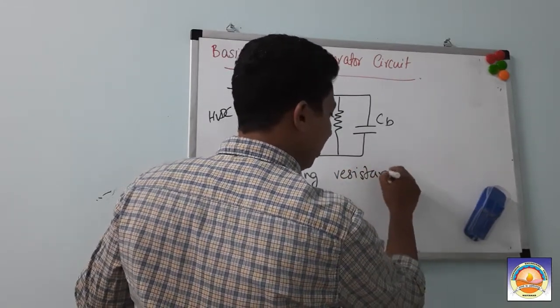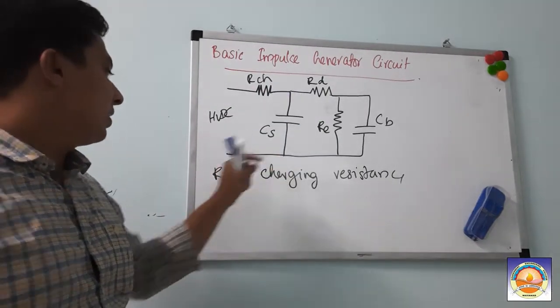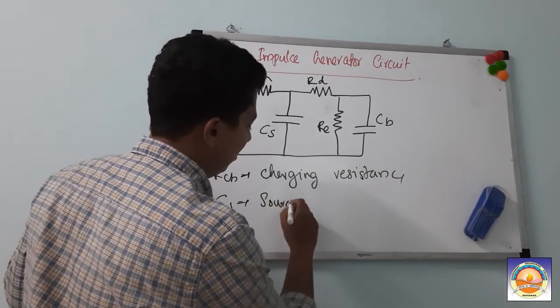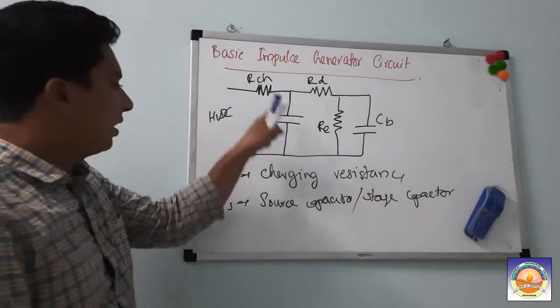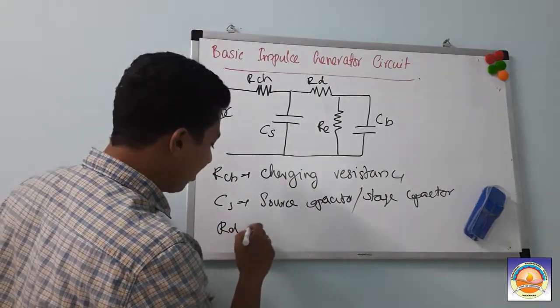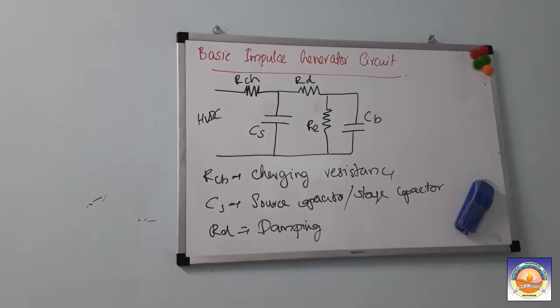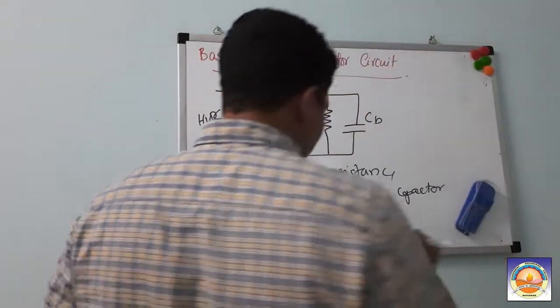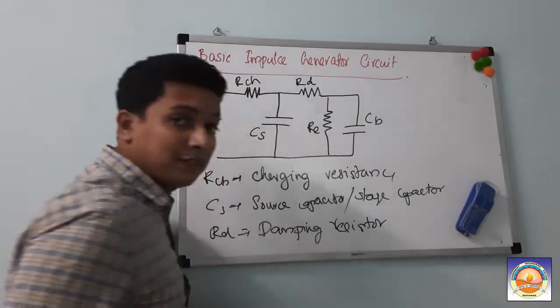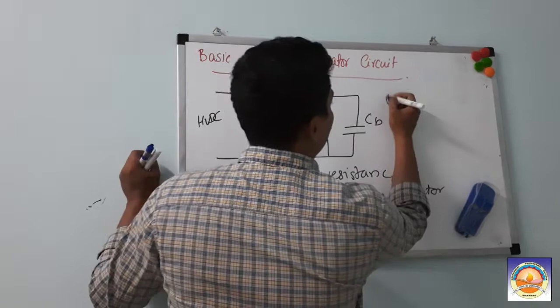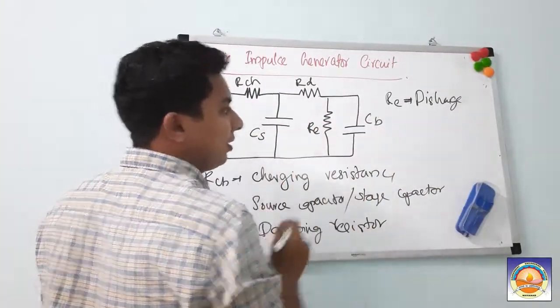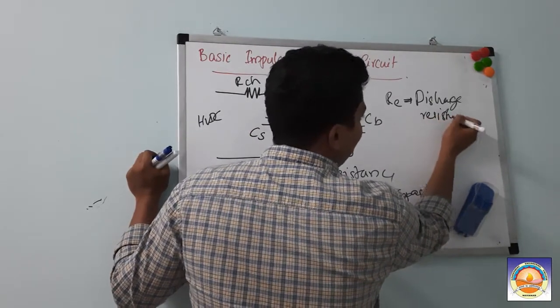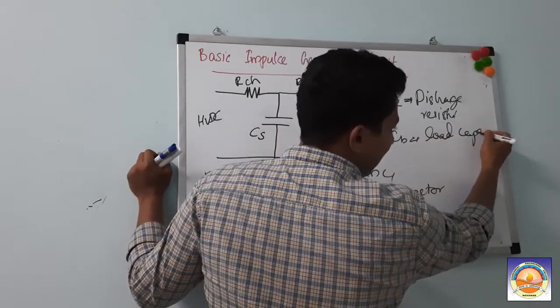The purpose of RCH is that when high voltage is applied, through this charging resistor your source capacitor CS — also called the stage capacitor — gets charged. Rd is known as the damping resistor. RE is the discharge resistor — it is the path through which CS as well as CB discharge. CB is the load capacitor.